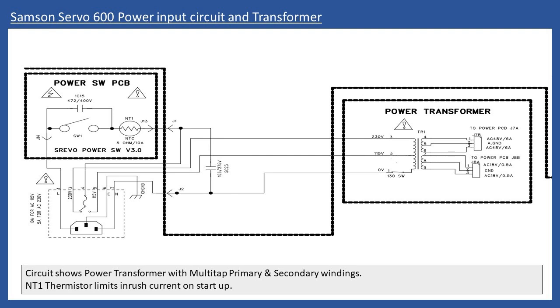So if it's a 230 volt input, they just wire the two windings in series. So then you connect 0, your neutral, then your 230 volts, and that becomes a single winding, which then of course provides the necessary power to the secondary windings.